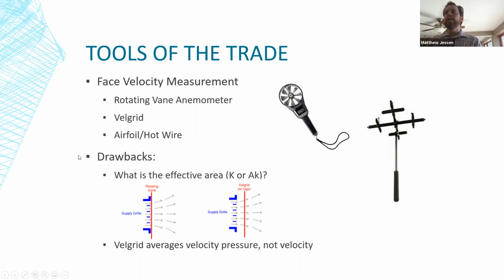Another thing to bear in mind is that the VelGrid averages velocity pressure, not velocity. And I didn't want to put a whole slide in here with the mathematical proof of this, but hopefully you engineers will recall that velocity is a function of the square root of velocity pressure. So if you take the sum of a bunch of square roots versus the square root of a sum, you get very different results. And taking the average of those velocity pressures and then calculating it is simply a less accurate way of getting your average velocity.